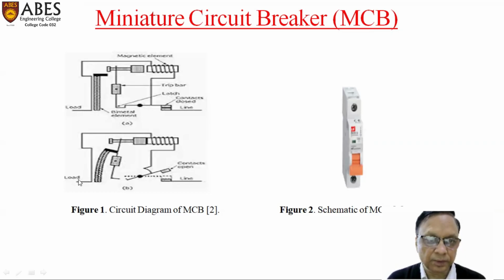The line gets opened to the load. The load is connected through the plunger onto the line with the help of these closed contacts. These contacts open once this bimetal strip bends and touches this trip bar. So the latch opens and the contacts finally get open. This is in case of overcurrent.